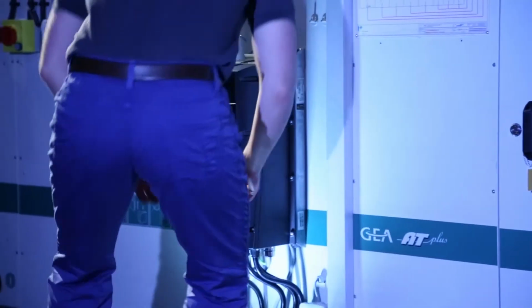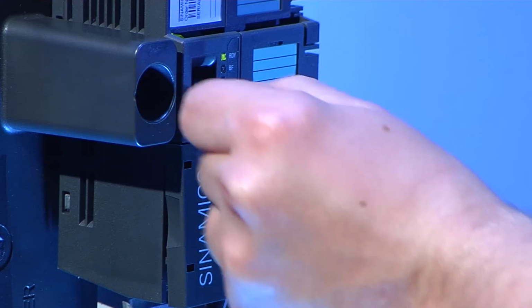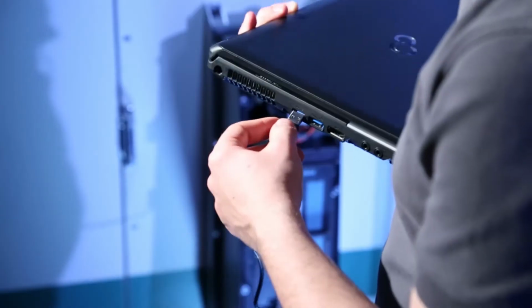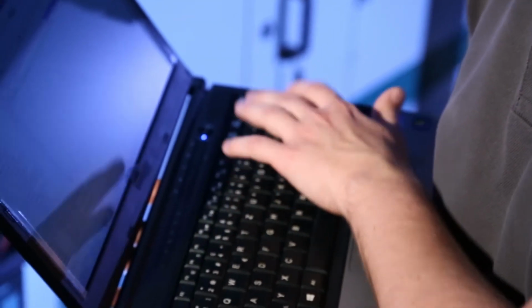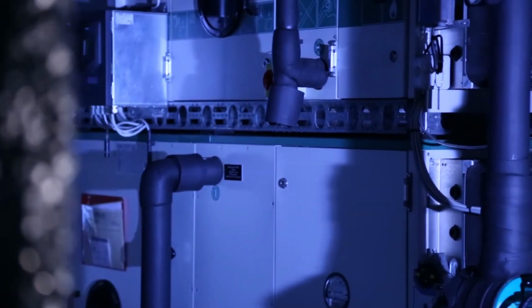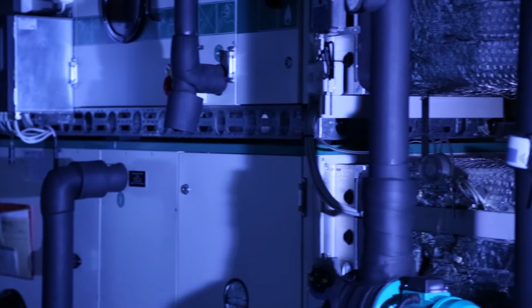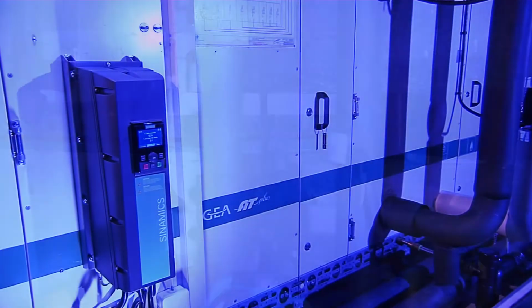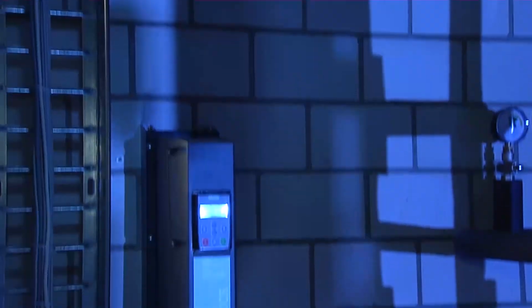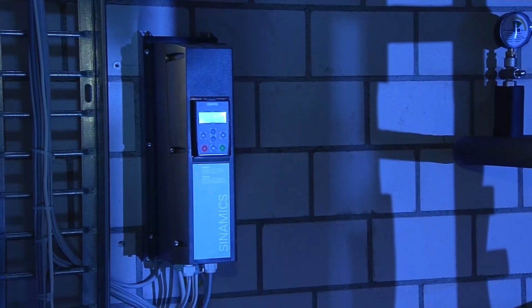As we have already shown, the starter commissioning software, for which a license is included in every bundle, makes it very easy to set up the G120P variable speed drive and to perform serial installations. In the field, the performance of your PID loop may sometimes be negatively affected by external factors, or you may have trouble with unexpected overvoltage faults because the setup of your drive is not optimized for your application.